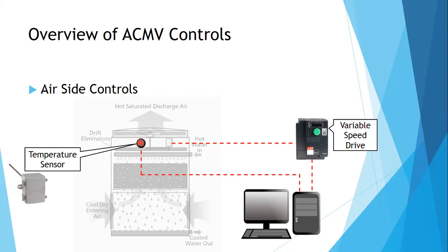But if the temperature here is higher than the set point, higher than 32, the variable speed drive will tell the motor, oops, I think you're a bit lazy. You need to ramp up a bit, run faster. So this temperature sensor, depending on the temperature set point, will tell the BMS. The BMS will evaluate. If it's lower than the set point, the variable speed drive will lower down. If higher than the set point, this variable speed drive will ramp up or increase.